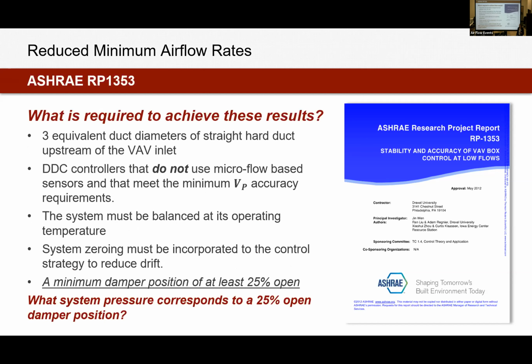So what was required to get there? We had to have perfect inlet conditions. We had to have those 3 equivalent duct diameters of straight hard duct into the VAV inlet. How many times are you actually either installing or designing with straight hard duct into an inlet valve? Always. I hope Tom always is. Usually people laugh at that because they're like, no, I never do that, there's no space, or yes, I'm going to put duct on there. So 3 equivalent duct diameters.